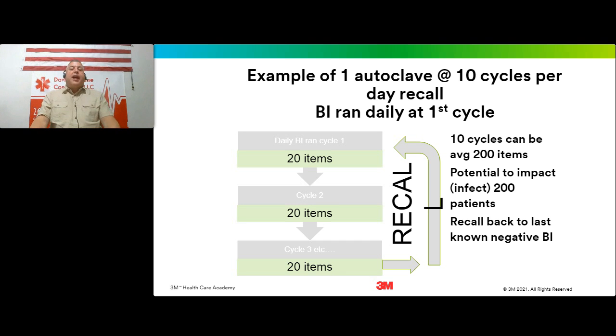So you ran 10 cycles. On the first cycle you ran a BI. The rest of the day there was no implants, therefore you didn't run any other BIs on this autoclave. So we're also going to assume that there was 20 items on each cycle that you ran throughout the day. So if we do the math, 10 cycles would average 200 items - 10 times 20, either way. So you have 200 items potentially out of one autoclave that day. Theoretically, you have 200 items going out to all different areas throughout the system that potentially could be used on up to 200 patients.